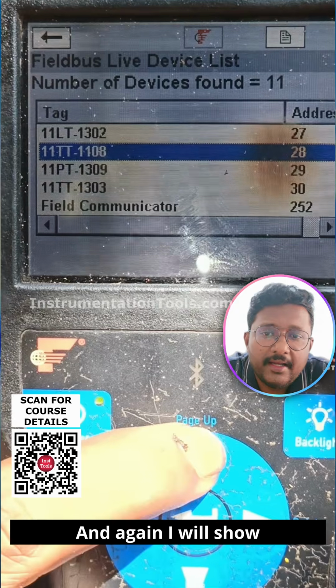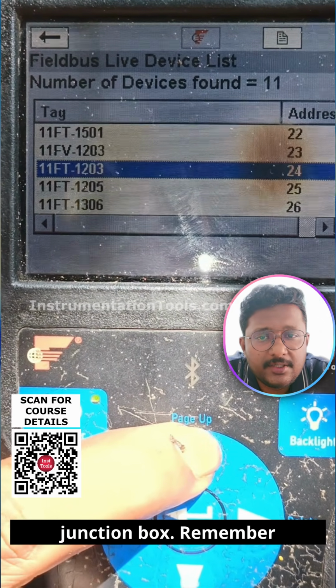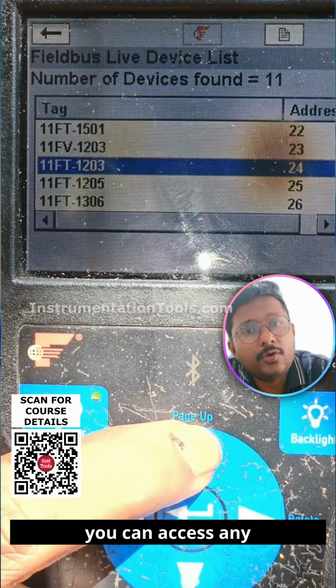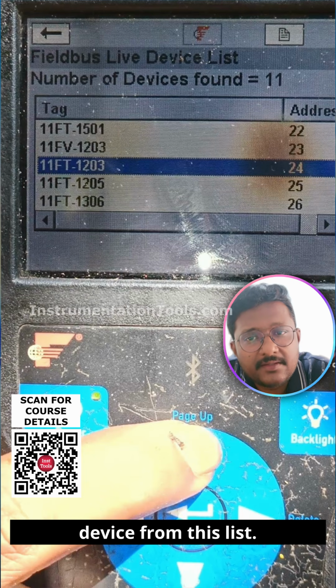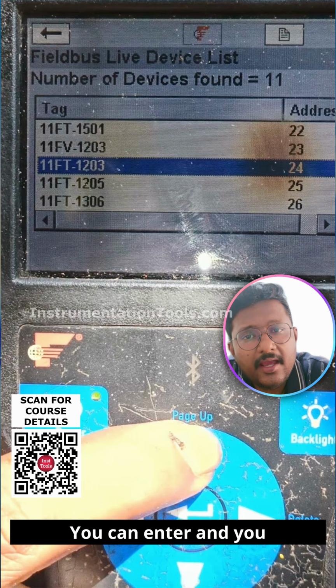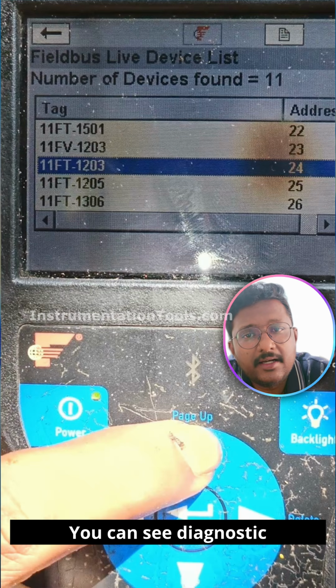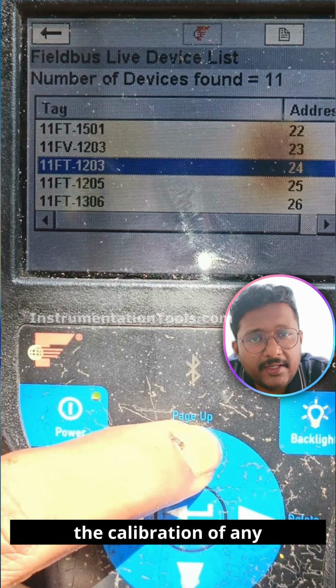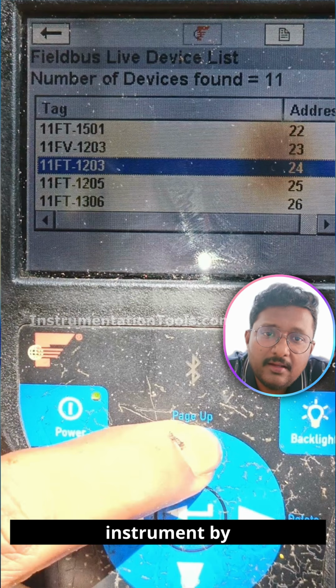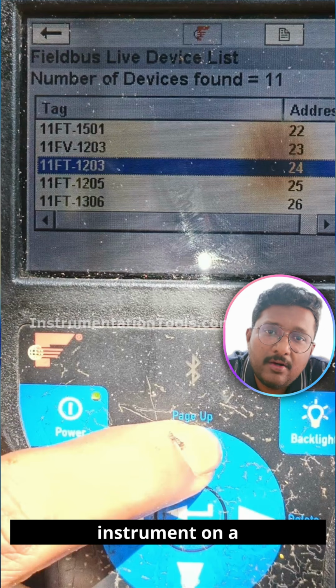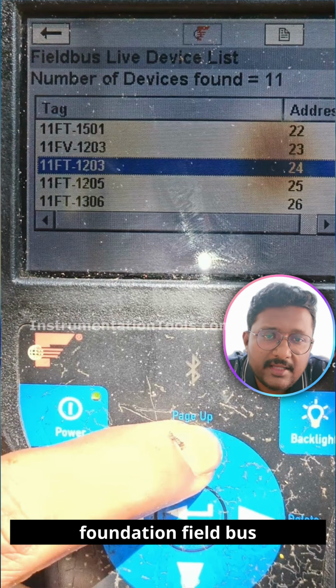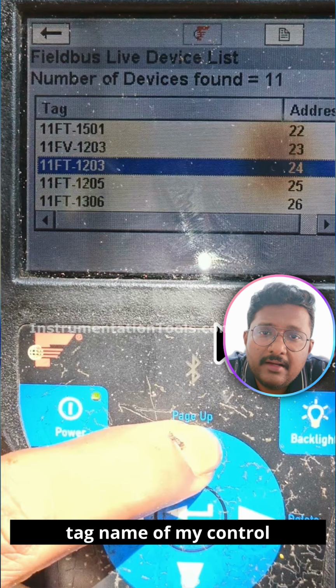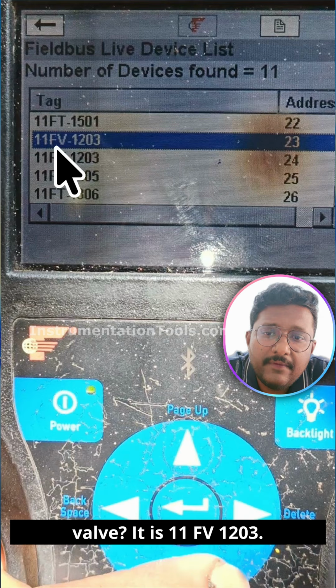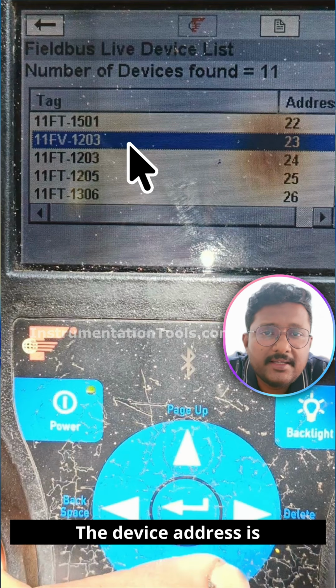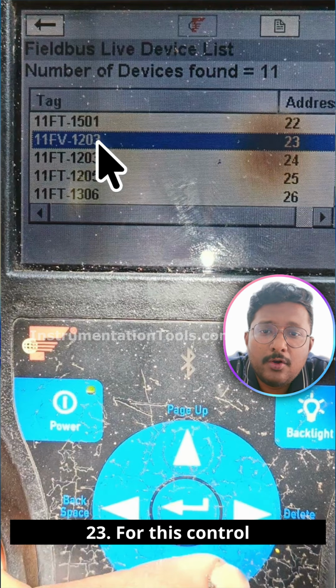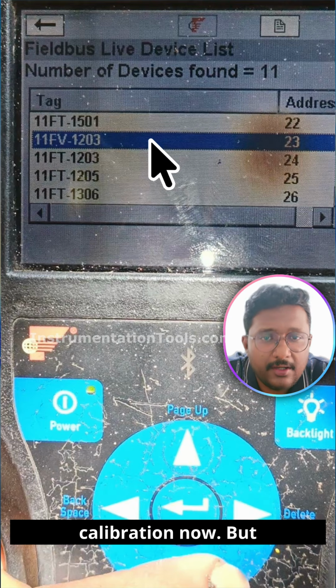And again, I will show you all my instruments connected in the junction box. Remember, you can access any device from this list. You can enter and view all the configurations. You can see diagnostic messages, or you can do the calibration of any instrument by connecting to any instrument on a Foundation Fieldbus segment. What is the tag name of my control valve? It is 11FV1203. The device address is 23. For this control valve, I want to do the calibration now.